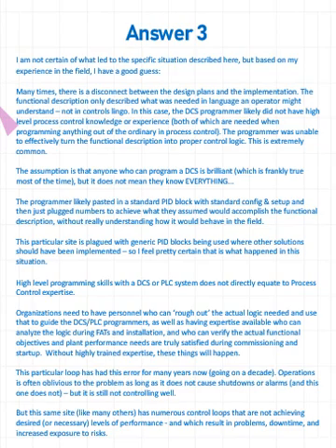So what happens at this particular site, they tend to pop in a generic PID block. They have kind of a standard library. They pick one of about four that seems the closest, and they're all basic blocks, and they throw them in and kind of hope they fit. It's kind of trying to fit a square peg in a round hole sometimes.